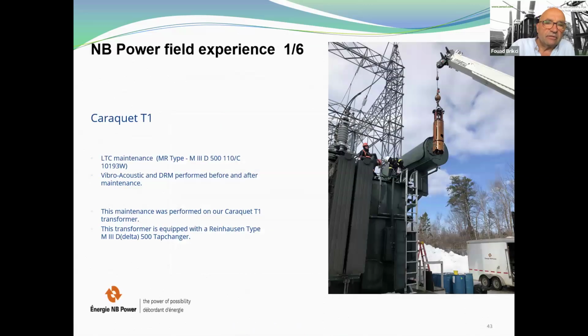Here you have an example of a New Brunswick Power field experience. They had an OLTC maintenance. It was an MR type M3D 500. On top of the vibroacoustic, they added the DRM, and they performed this test before and after maintenance.